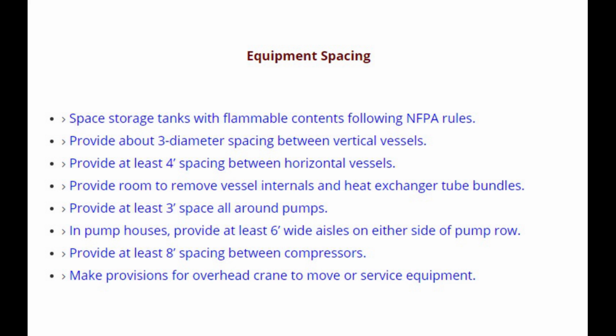Good practice for equipment spacing. Number 1. Space storage tanks with flammable contents following NFPA rules. Number 2. Provide about 3 diameter spacing between vertical vessels. Number 3. Provide at least 4 feet spacing between horizontal vessels. Number 4. Provide room to remove vessel internals and heat exchanger tube bundles.